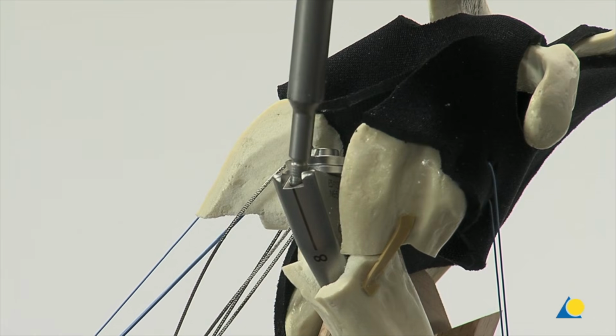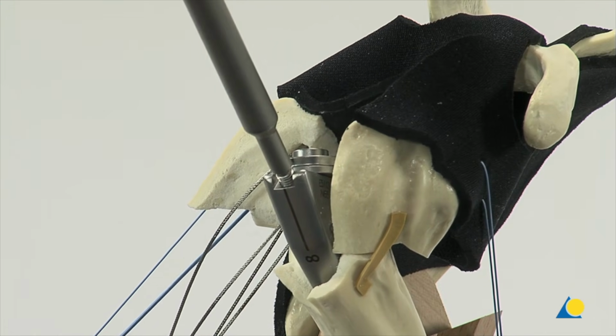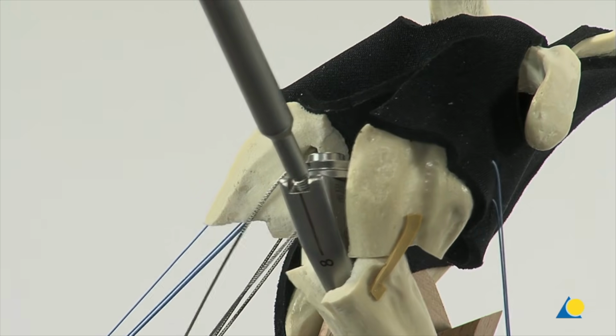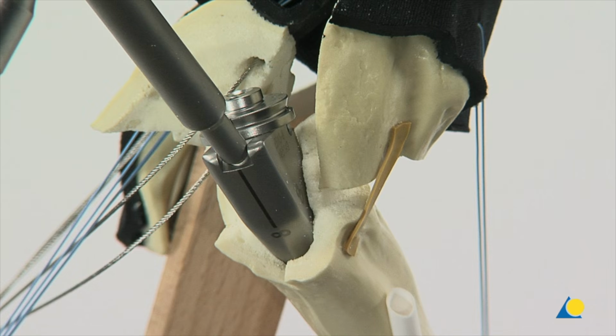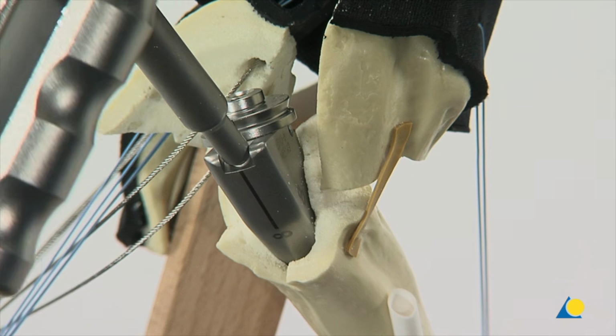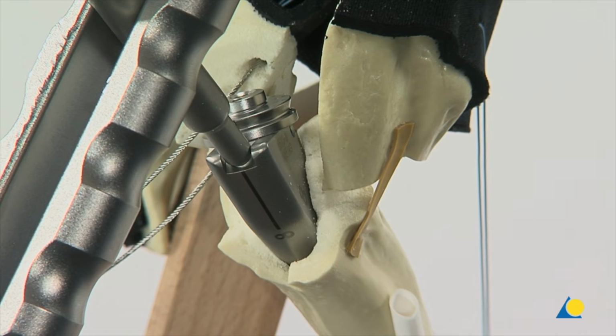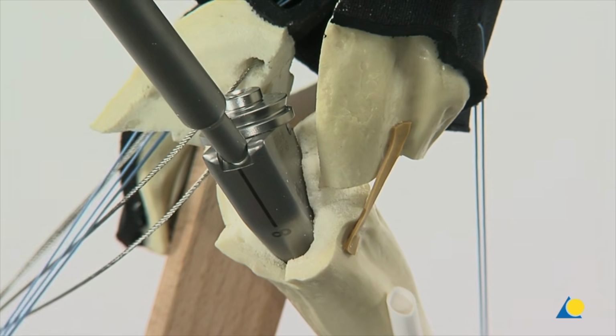The inserter extractor is mounted on the trial stem. To avoid possible damage to the thread, it must be ensured that the inserter extractor is fully threaded into the trial stem. With light taps against the inserter extractor, the trial stem can be backed out.